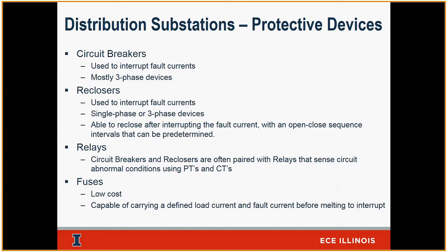A recloser is similar to the circuit breaker in terms of it's an interrupting device. It's a protective device. It does the same function that I described for the circuit breaker. One of the main differences is it doesn't have to be a three-phase device, meaning it can operate on a single-phase basis. I can open A only, or B only, or C only, or A and B, right? Or I can operate it three-phase. The other difference is I can program it to do a reclose sequence. So we just talked about how if I have a fault, two lines could cross. So say a tree limb came across, sat on a line, pushed it, made two lines touch.